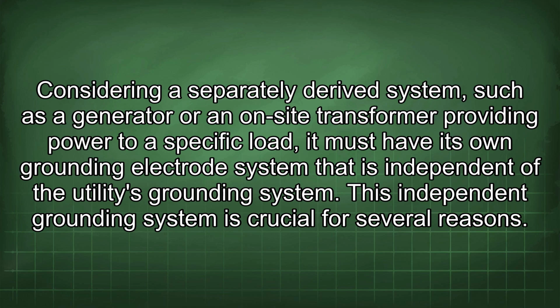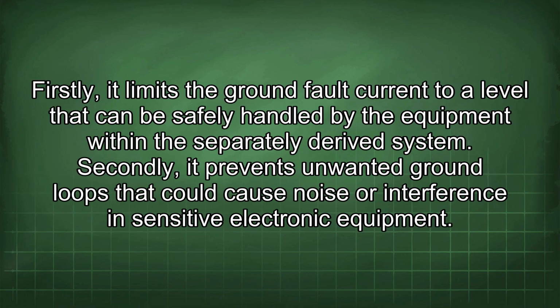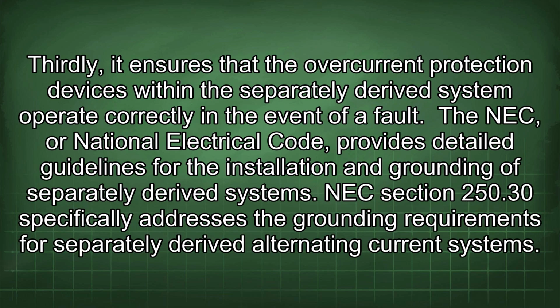Considering a separately derived system such as a generator or an on-site transformer providing power to a specific load, it must have its own grounding electrode system that is independent of the utility's grounding system. This independent grounding system is crucial for several reasons. Firstly, it limits the ground fault current to a level that can be safely handled by the equipment within the separately derived system. Secondly, it prevents unwanted ground loops that could cause noise or interference in sensitive electronic equipment. Thirdly, it ensures that the overcurrent protection devices within the separately derived system operate correctly in the event of a fault.